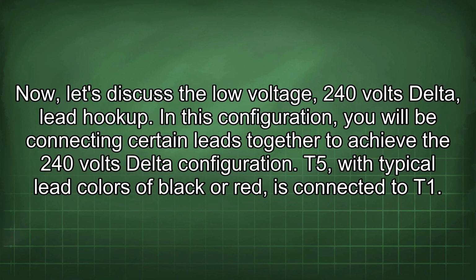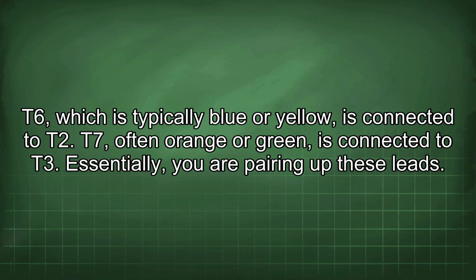Now let's discuss the low voltage 240 volts delta lead hookup. In this configuration, you will be connecting certain leads together to achieve the 240 volts delta configuration. T4, with typical lead colors of black or red, is connected to T1. T5, which is typically blue or yellow, is connected to T2. T6, often orange or green, is connected to T3. Essentially, you are pairing up these leads.